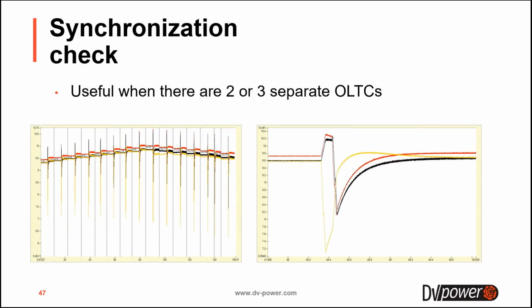or simply, by the time, the mechanism loses its accuracy, and the tap changers become desynchronized more than they should be. This is possible to check when using a 3-phase device. The 3-phase device has the option to check the synchronization, and here on the left side you can see how it looks when you have a desynchronized tap changer.